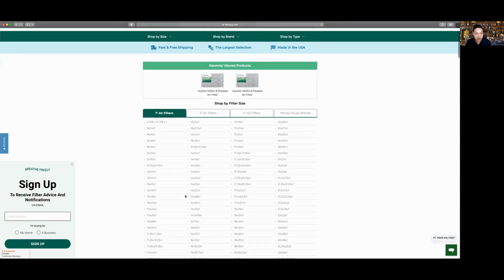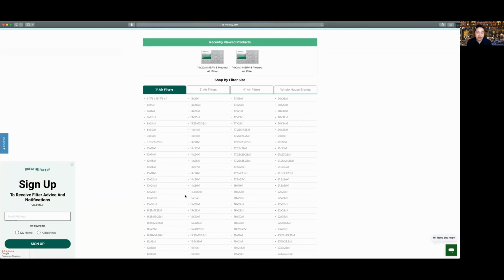Typically, when you start with your air filters, you look at the existing system you already have and see what air filters you have. The standard sizes are 1 inch, 2 inch, and 4 inch. The 4 inch is really thick. They're usually MERV 11 or MERV 13. You'll know what size to use by taking out the existing filter. Your furnace is located in one of three places: the hallway, the garage, or the attic. You go to your furnace and find the return, and that's where your air filter is going to be. So you take out the air filters and find the exact matching size.